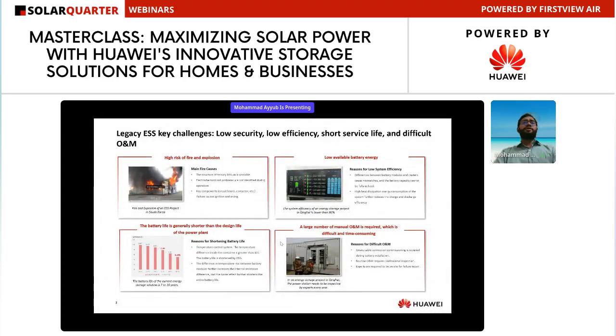Coming to safety, coming to the key challenges for energy storage: wherever we have lithium batteries, there is always a possibility of fires, always a possibility of thermal runaway, maybe because of temperature issues, lack of awareness about selection of the right technology, or improper system design or interconnection. It could be circuit board issues or connector issues. There could be n number of issues. The major reason we see in the market, especially across the globe, is thermal runaway, where a fault at the cell level or battery pack level escalates into the overall system level.